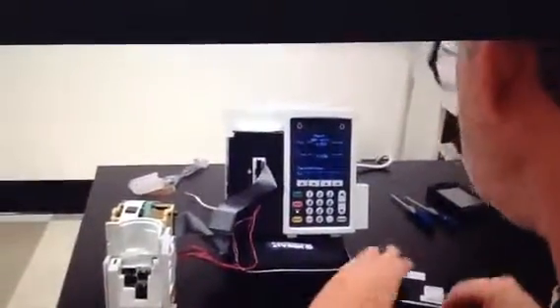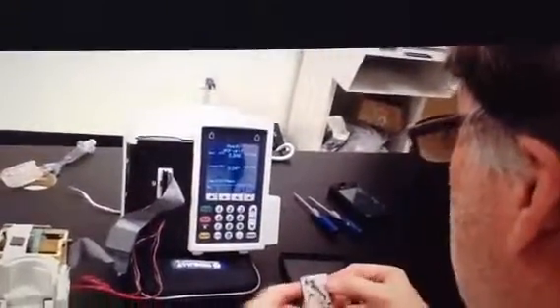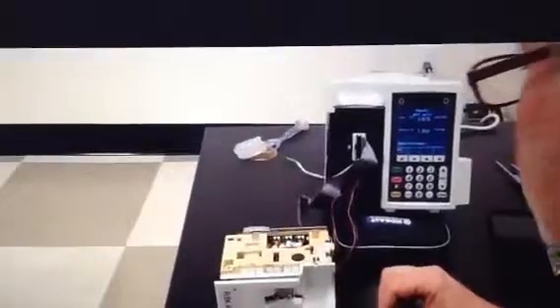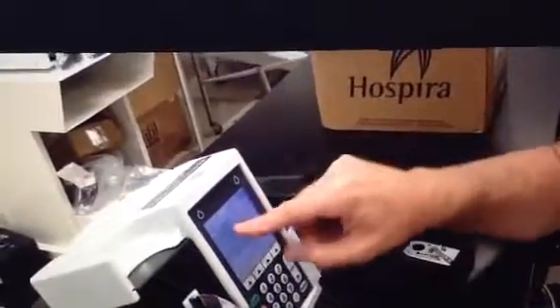We hear the mech initialize, and it tells us to use the 0 psi fixture. So we have these two metal cassettes. One is calibrated for 0 psi, and the other is calibrated for 10 psi. We open the door in the mechanism and insert the fixture. Now, the first thing we need to do is set our 0, and it shows us that we need 0.020 to 0.080 for the distal pressure. And so this pot on the left-hand side is for distal.